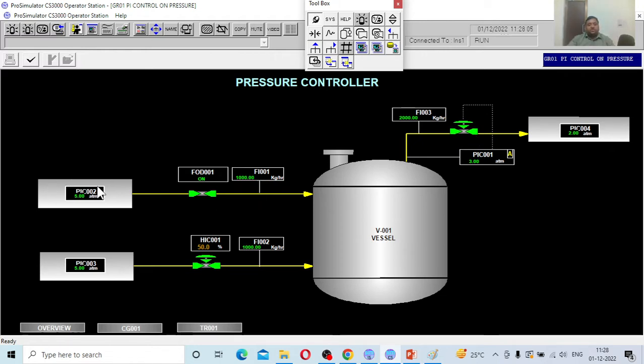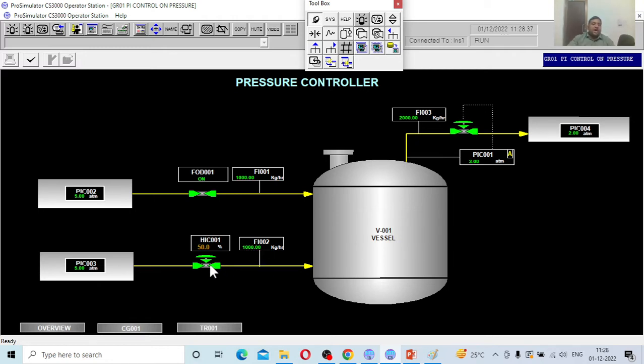There are two process lines — PIC 002 at 5 atm and PIC 003. One line has flow coming at higher pressure through a non-return valve, and the other line has a flow rate of 1000 kilogram per hour, with the second line also at 1000 kilogram per hour but manually controlled. The manual control valve is presently 50 percent open. In the vessel, they have to maintain the pressure at 3 atmospheres, because both lines are at 5 atmospheres but the utility requires 3 atmospheres.